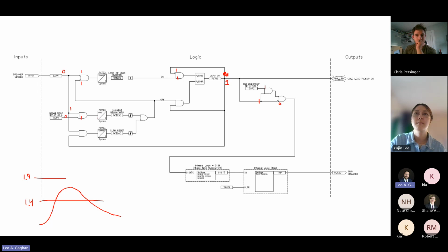So then we've got a time delay here of 15 seconds. So basically what we've said is, the cold load pickup is on. We dropped below that 1.4 amps, and we've been below that 1.4 amps for 15 seconds. Okay, we got a 1 and a 1. What we're going to do is send a pulse, and we're going to have a 1 come through, and we're going to reset that logic. So now, after it is normalized for 15 seconds, we can turn that logic off and go back to our normal pickup. So now we're back to a 0 here. That part doesn't really mean as much. I got a NOT gate. We've got a 1. We're back to our normal pickup.